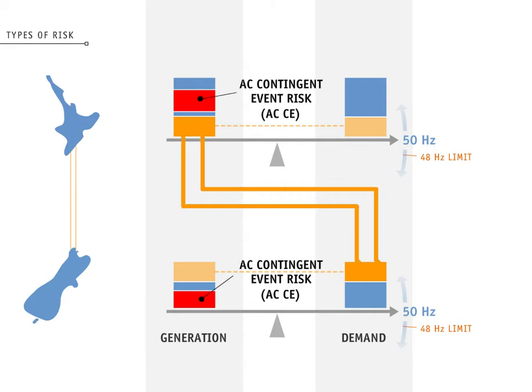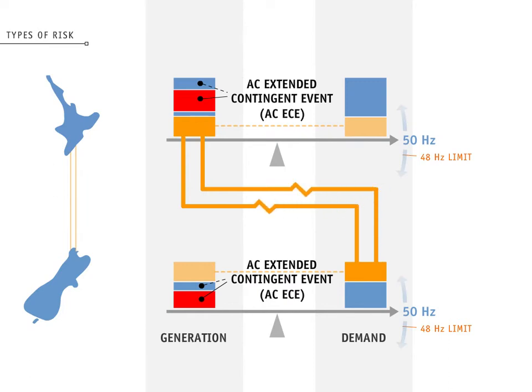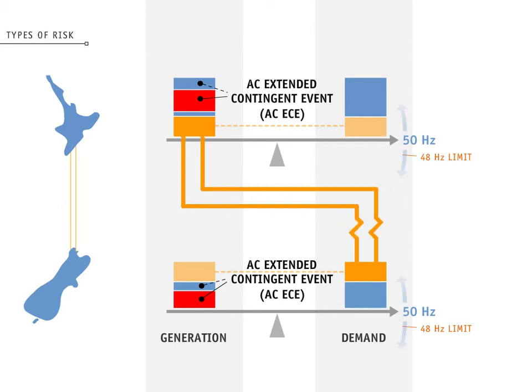An AC contingent event, or ACCE, is defined as losing the largest single unit of generation. An AC extended contingent event, or AC-ECE, is defined on a station basis that can include losing an interconnected transformer or a bus bar fault, which could be the loss of multiple generators.